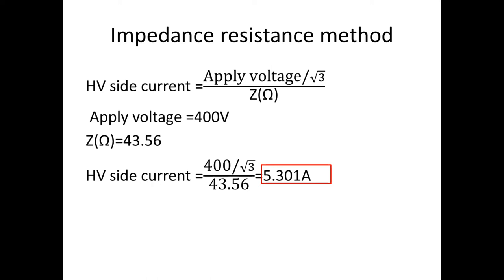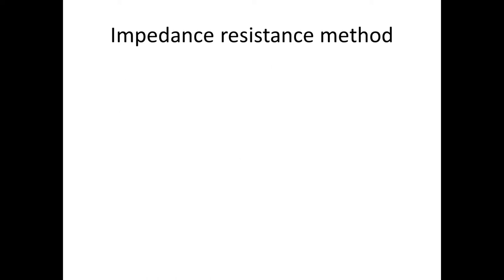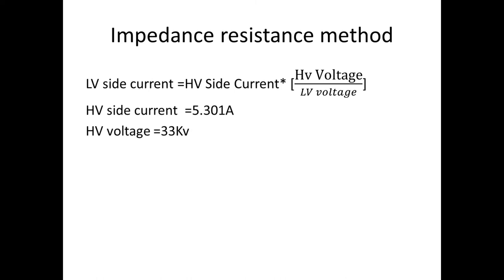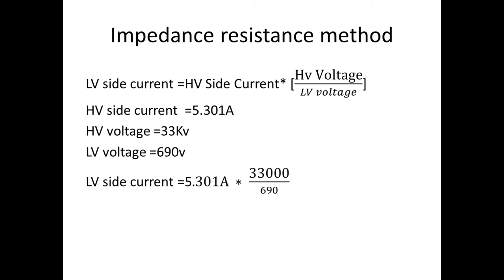Calculating, we have 5.301 A on the HV side. For the LV side current, we use: HV side current × (HV voltage / LV voltage). Applying the current value of 5.301 A gives an LV side current of 253.52 A.